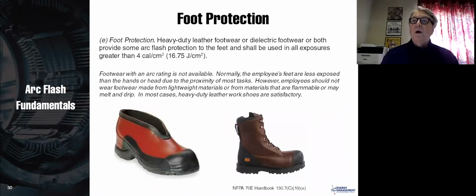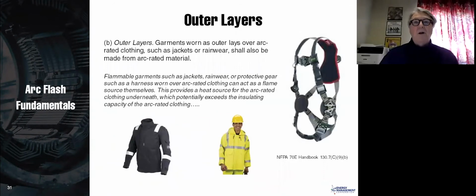Heavy-duty leather footwear or dielectric footwear provides some arc flash protection to the feet and shall be used in all exposures greater than 4 calories. Footwear with an arc rating is not available. Normally, the employee's feet are less exposed than the hands or head due to the proximity of most tasks. However, employees should not wear footwear made of lightweight materials and so forth. So basically, our standard PPE includes good industrial leather work shoes, but they're not going to have an arc rating. And our experience is that that's okay, that they do tend to protect people, but again, a little bit loosey-goosey in the standards. Outer layers.